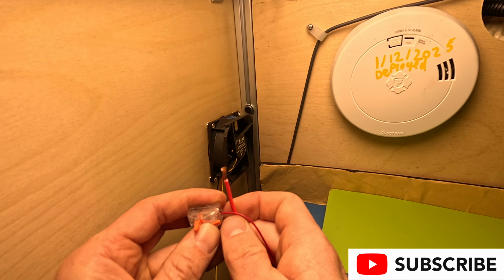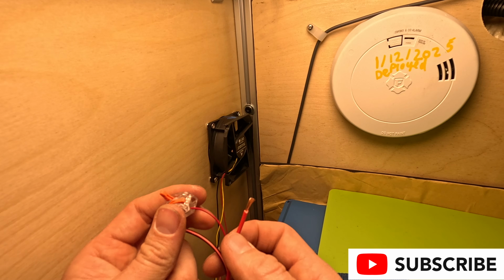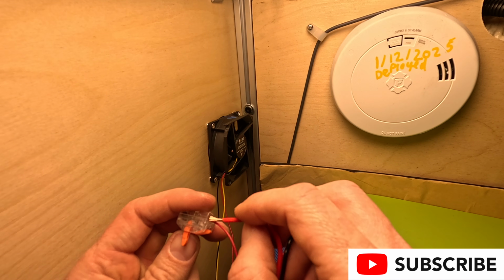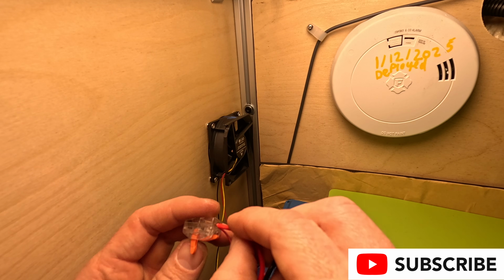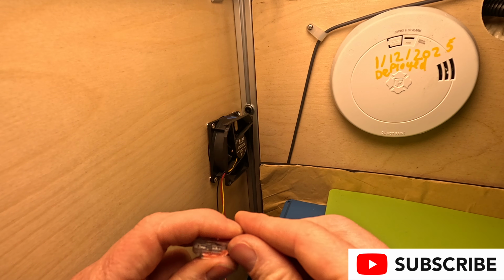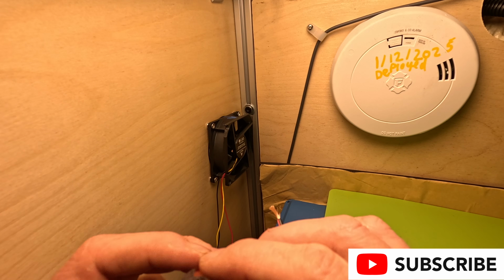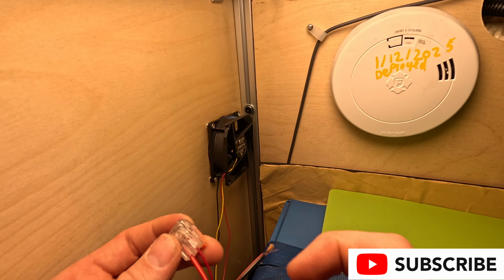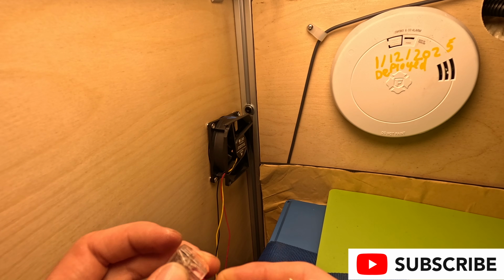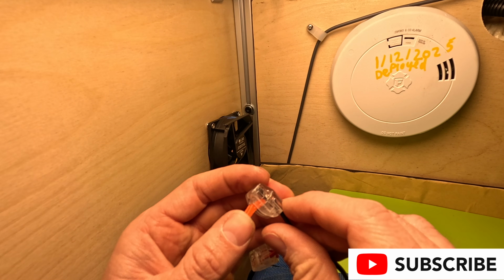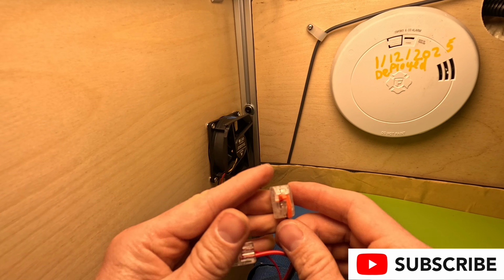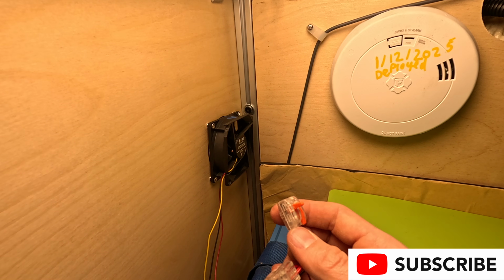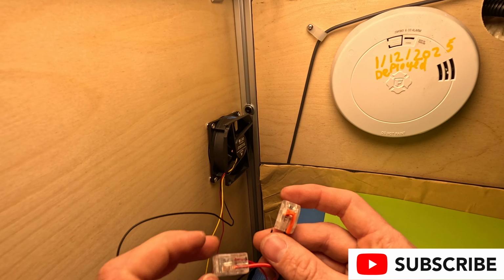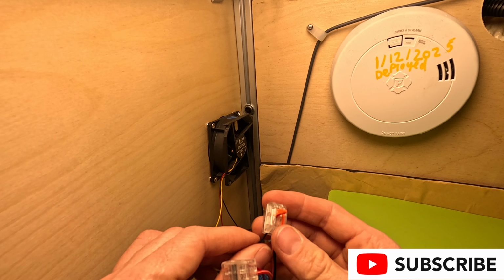Using some Wago connectors, we are going to create a connection for our red wires and a connection for our black wires. These connections will go back to a DC panel where we will fuse at 3 amps, after which we take that positive and negative wire and run it through our relay that's plugged into our Cerbo GX.